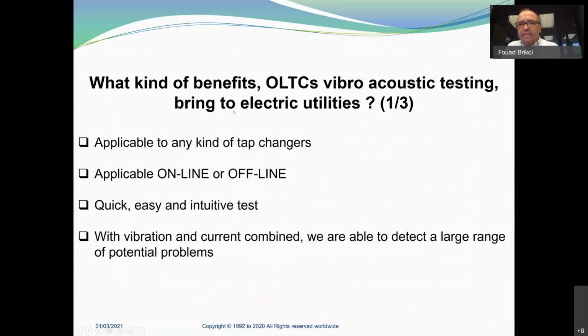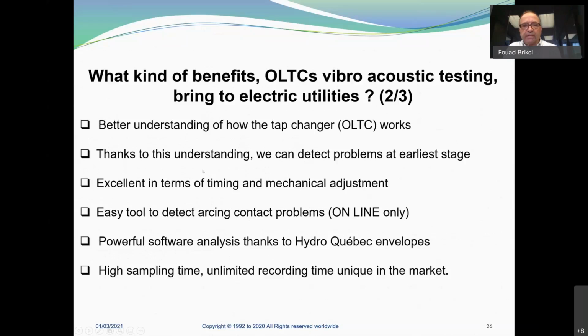And what kind of benefits does OLTC vibroacoustic bring to electric utilities? In fact, we can count 14 of them. Here I present the 4 main: applicable to any kind of tap changer, applicable online or offline, a quick, easy, and intuitive test, and with vibration and current combined, we are able to detect a large range of potential problems. I have more here. You have 6.